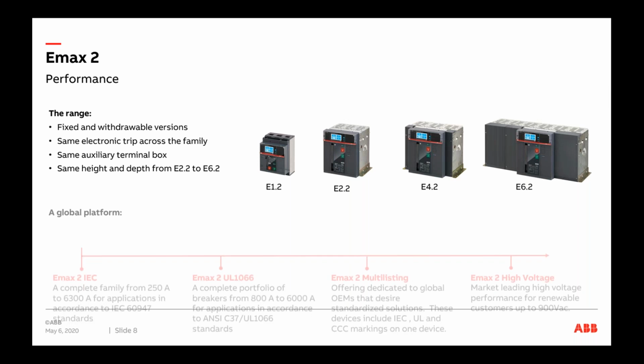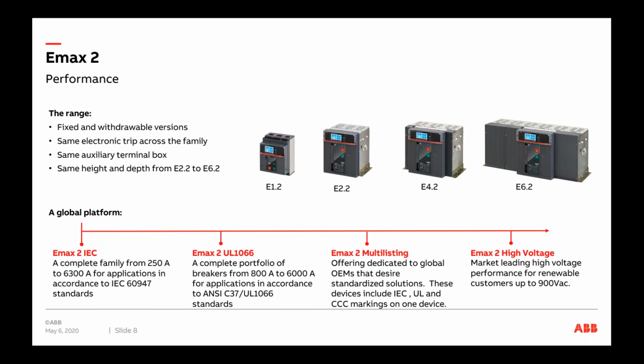Now, in terms of the particular breakers, the breakers are from 250 amps all the way to 6,300. Of course, they are in accordance to 60947-2. We also have certain high voltage Emax 2s, like I mentioned a bit earlier, which allows us to go all the way up to 900 volt AC. They are special breakers with the same technology of the current Emax. The current Emax is generally rated up to 690 volts, obviously with similar current ratings, but different short circuit and KA ratings and ICW ratings.